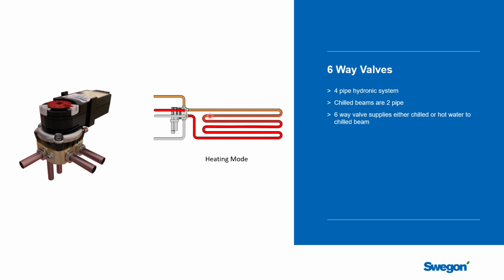So it's a good thing to point out here is that when you switch from one system to the other, you are definitely going to flush water from one system to the other. Not a lot, but you will do it. So both loops have to be, for instance, straight water. If you had a situation where your chilled water loop had some glycol in it because the chillers were outdoor and you wanted to protect it, this would not be a good application. You would end up flushing the glycol slowly but surely out of the chilled water loop and into the heating loop. So it's always a good requirement that you have straight water in both systems.